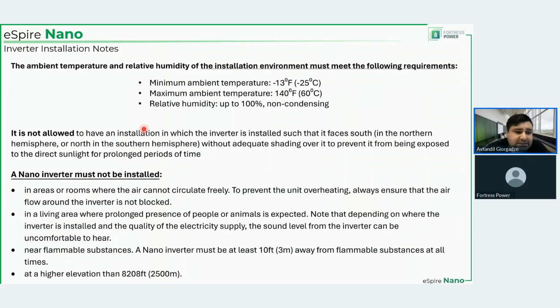Now, where the nano inverter must not be installed: in areas or rooms where the air circulation is limited, again, because we don't want the unit to overheat. That's why it says always ensure that the airflow around the inverter is not blocked, because again, this is an air-cooled unit. Also not in a living area where prolonged presence of people or animals is expected, note that depending on where the inverter is installed and the quality of the electricity supply, the sound level from the inverter can be uncomfortable to hear. That is again because these are air-cooled, those fans come on, and when they're working at full blast, they can be quite loud.